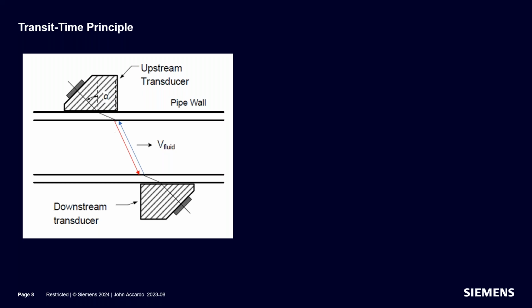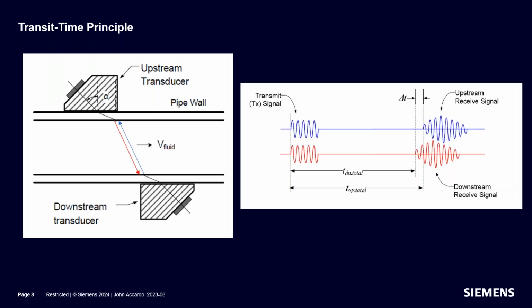But what happens is when fluid is moving in the pipe, the effect of the fluid velocity works to accelerate the sonic beam in one direction and delay it in the opposite direction. As a result, there's a net time difference. So what you see on the right now is the two transmit signals shown synchronized together, even though they're happening alternately. They're not happening at the same time. But they start out synchronized to one another, and you'll see to the right, the receive signals are shifted from one another. Now, if there was no flow in the pipe, they would be perfectly aligned with each other because it would take exactly the same amount of time to go one way as the other.